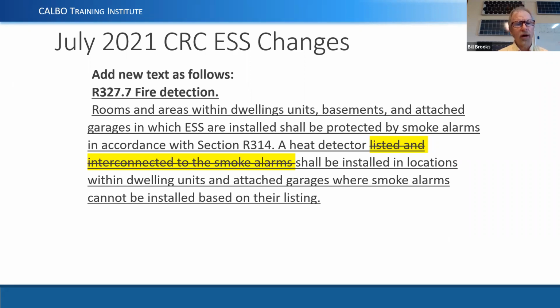If we're going to install energy storage inside the dwelling, then we need to have smoke alarms to let people know that if we have a problem, to alert people. And if it's in an attached garage, somewhere where a smoke alarm can't be used according to its listing, then we need some type of a heat detector. And there's been a lot of discussion about this, and we don't really have time to go into a lot of detail about heat detectors and heat alarms and things like that.